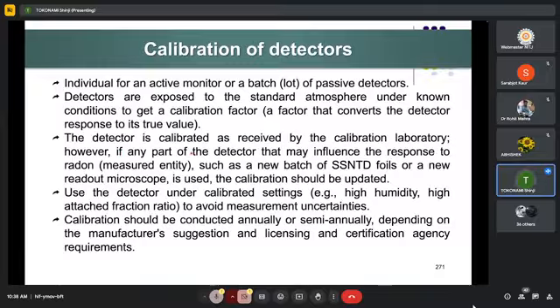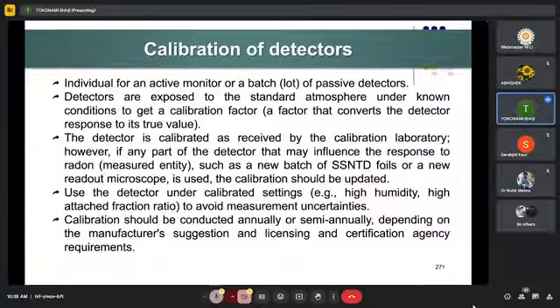However, if any part of the detector that may influence the response to radon, that is the measured entity, such as a new batch of solid-state nuclear track detectors, foils, or a new readout microscope is used, the calibration should be updated. Use the detector under calibrated settings, high humidity, high attached fraction ratio to avoid measurement uncertainties. Calibration should be conducted annually or semi-annually, depending on the manufacturer's suggestion and licensing and certification agency requirements.